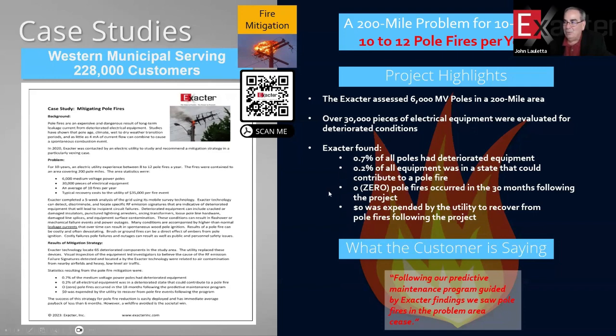And 0.2% of all the equipment was in a state that could contribute to a pole fire. So now we had it narrowed down to these few insulators out of the 30,000 devices, 0.2% of them were involved. And that represented about 65 devices themselves. So the utility changed out all 65 devices with brand new ones. And from that point forward, for 3.5 years now, they haven't had one pole fire in that 200 miles. So that's a real telling project with history, events, and then a change in the history to a new future for that utility. It's amazing, and you can do that everywhere.